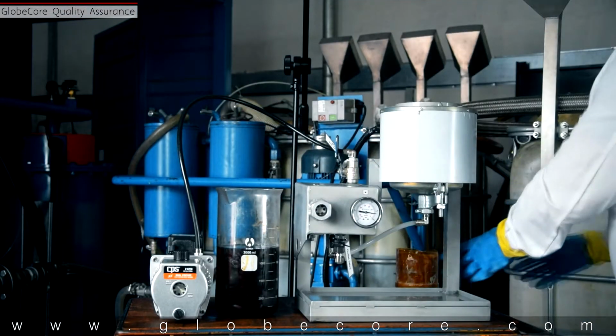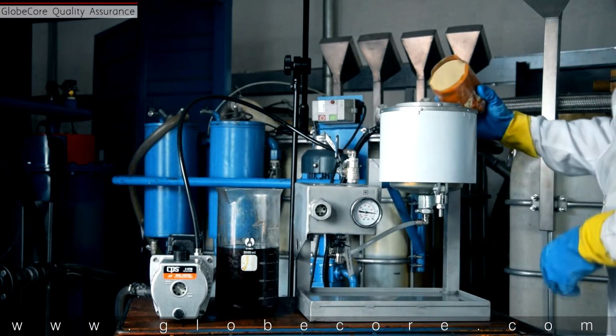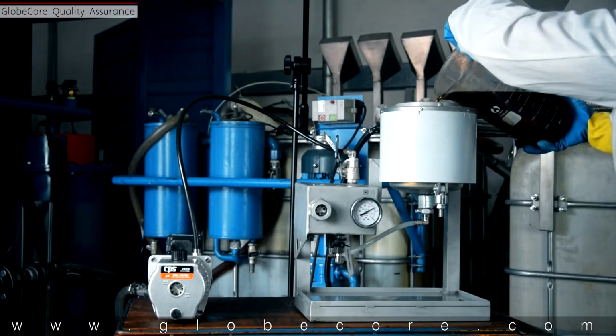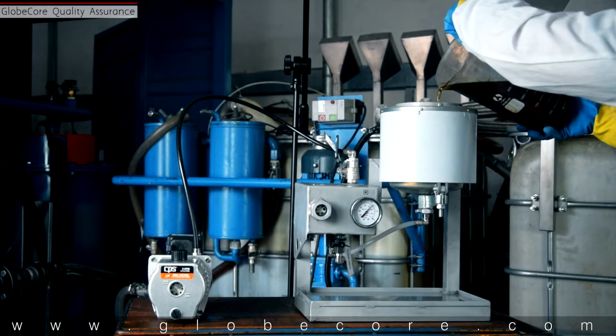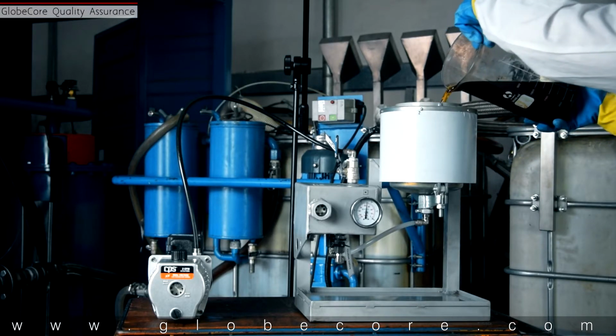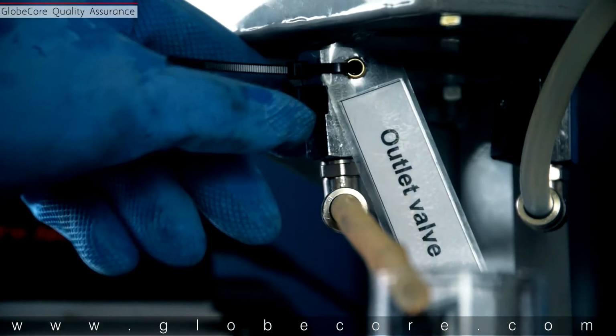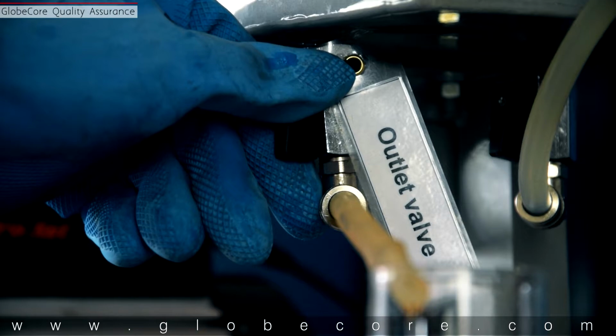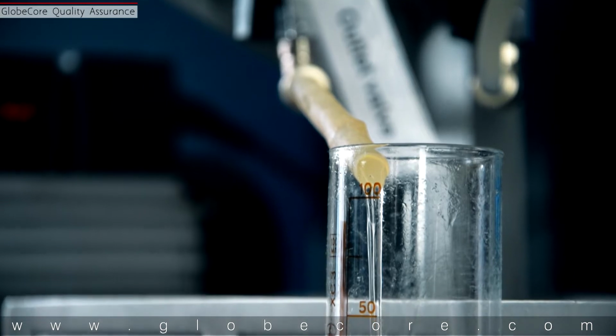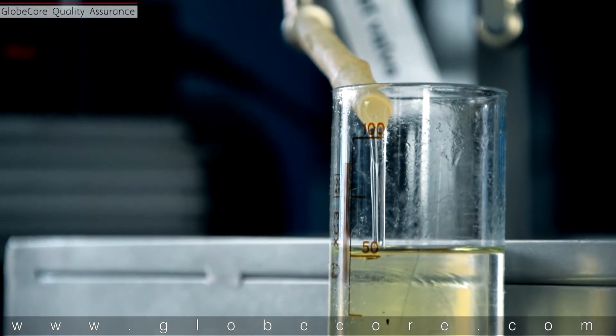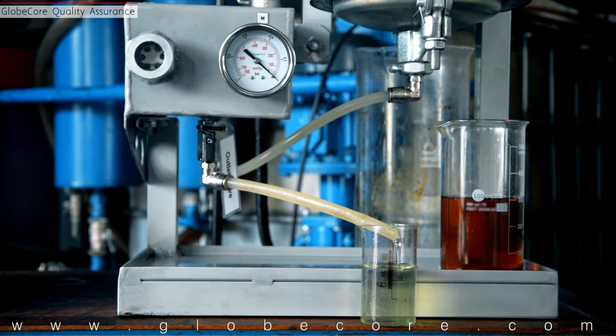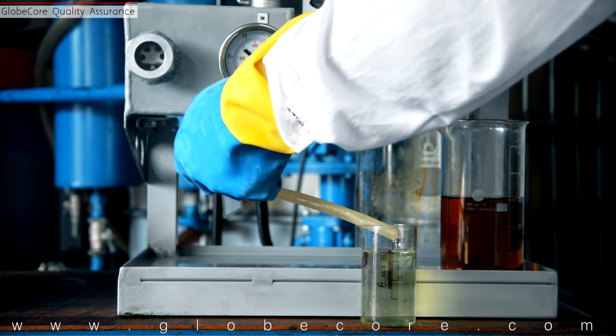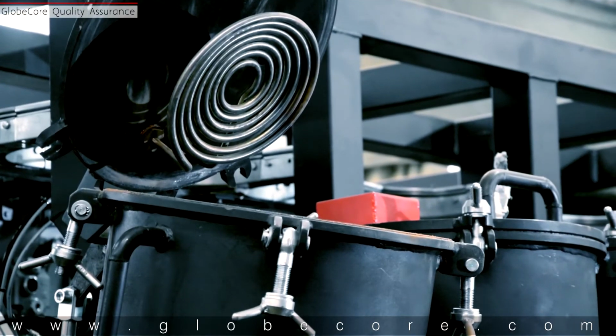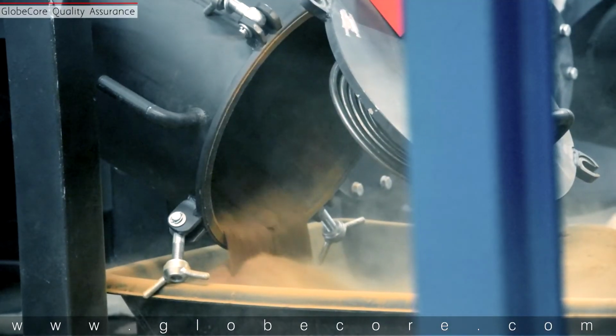Increase of transformer oil dielectric strength from 20 to 70 kV. Removal of decomposition products and acidic substances. Clarification of oil, improvement of aging stability, and reduction of gas dissolution. Improvement of oil characteristics even after one pass through the unit. Lifetime extension of both the oil and the transformer while the oil is in use. Savings on buying new oil and disposing of used oil. Reactivation of saturated sorbent and its reuse for transformer oil regeneration.